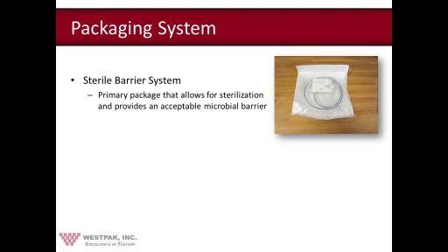Just so we're on the same page, I'm going to briefly go over a definition of a packaging system. For medical devices, a packaging system comprises a sterile barrier system and the protective packaging. The sterile barrier system is typically your primary package. This is your package that is in intimate contact with your product and provides the sterile barrier. This is the package that allows for sterilization and provides a microbial barrier. So these are usually your breathable pouches and trays, which is most commonly a spun polyolefin material, also known by its trade name as Tyvek.